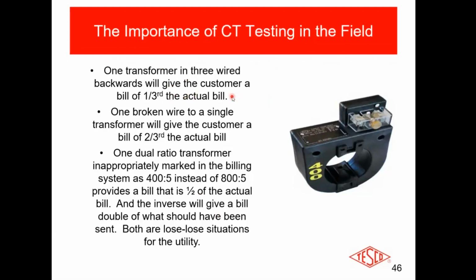If you got 3 transformers wired up perfectly, nice in a row, you'd think it would be pretty easy to see that one of them is backwards. But if you've ever been out in the field, which most of you guys probably have, when you open up some boxes, they are not laid in there very nicely. There's one transformer near the top, there's one on the left, and there's one on the right. Are they all wired up correctly? It's a little tough to see unless you follow the wires and check the white dots.